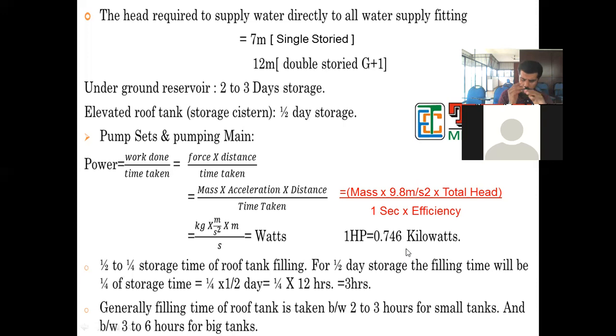So, if you have 1,000 liters of overhead tank, how much time does it require, or how much time does the overhead tank take to be filled or full? Okay, we can see how it is. Normally it is taken as 1/2 to 1/4 of the storage time of the roof tank. Which means that for a half day storage, the filling time will be 1/4 of the storage time. This we can take in the range of 1/2 to 1/4 of the storage time of roof tank filling.